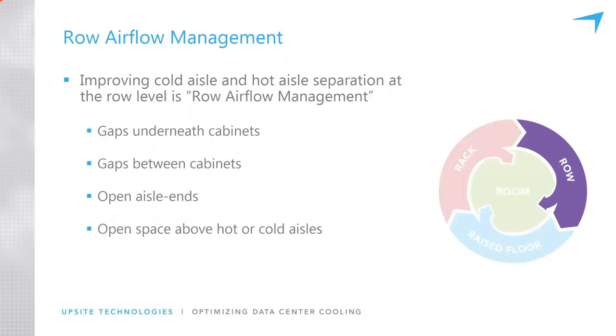So today's presentation is really focusing on the row level. And what does that mean? It means the spaces around the row, the gaps underneath cabinets, gaps between cabinets, open aisle ends, and the space above either the hot or the cold aisle.